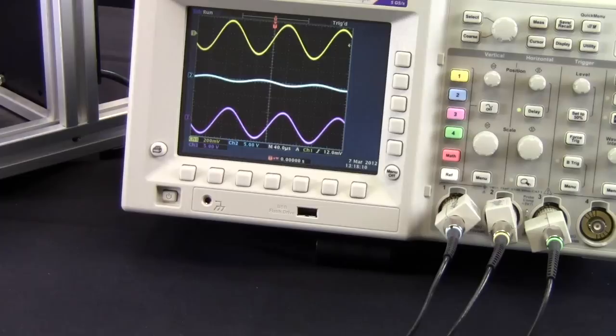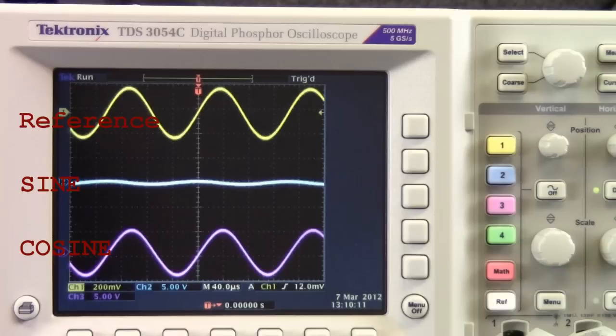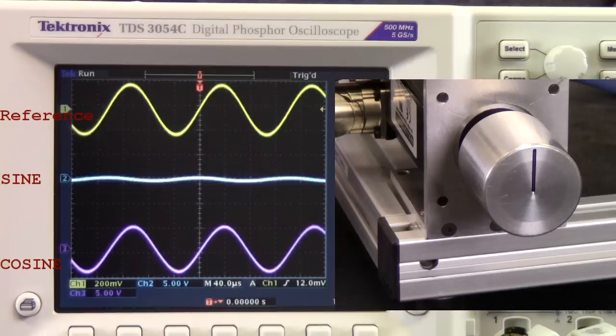We will use an oscilloscope to view what goes on inside a resolver. Channel A is connected to our reference signal, channel B is connected to our sine output, and channel C is connected to our cosine output. Start with the motor at zero position, or what is called the zero crossover point. Sine is at zero amplitude, and cosine is at peak amplitude and in phase.